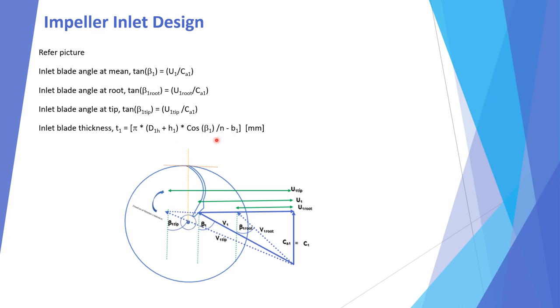The inlet blade thickness T1 is calculated using the formula: T1 = π(D1h + H1) × cos(β1) / N − B1. I will make a separate video explaining how this is derived, but for now this formula is used to calculate the inlet blade thickness of the impeller.